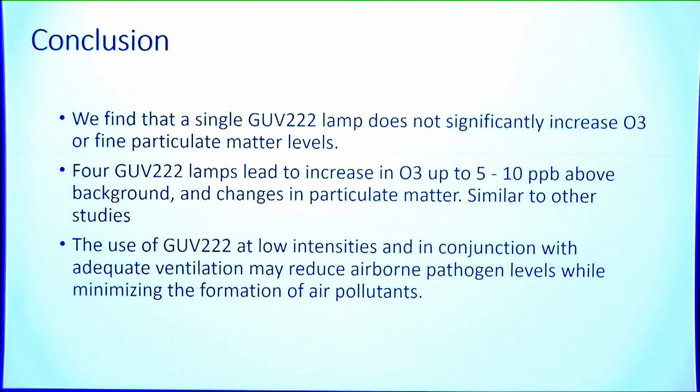So in conclusion, we suggest that a single lamp does not significantly contribute to the ozone level increase and particulate matter increase. However, under the 4-lamp scenario, there's about a 5 to 10 parts per billion ozone level increase compared to the background level in the lounge, and some increase of the particulate matter level as well.